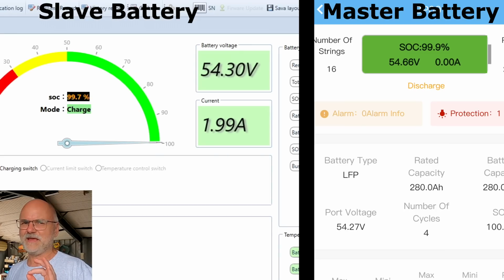Now you will see the weirdness of this whole system, because the slave battery is now recharging to 55.2 volts, while the master will not, because charging is disabled still. We've got a warning, an alarm there from the last microcycle, and you can see they are acting completely independent now.